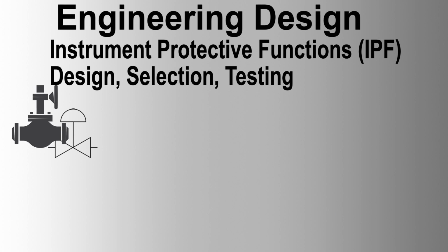If not required, it should be indicated in the requisition. Input force status to DCS. For each hardwired digital trip input, trip alarm to DCS, input diagnostic status for inputs with short circuit or line monitoring to DCS, maintenance override from DCS, feedback on maintenance override to DCS, first up indication to DCS, input force status to DCS. For fire and gas inputs, details depend on the detectors used and should be indicated in the requisition. For each hardwired acknowledge and first up reset and lamp test input, no signal to DCS required.